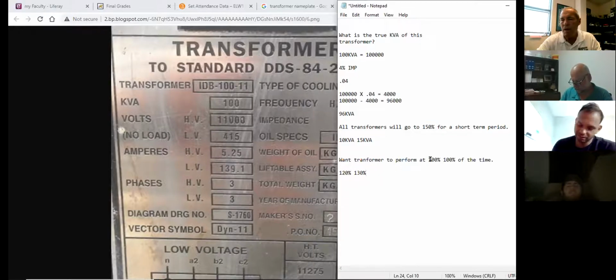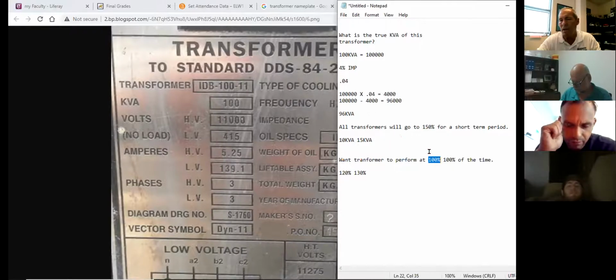All right, goes back to a nice calm day, it's 100%. I think you guys got to realize here, my 100 kVA transformer is going to cost me about $10,000 a piece. Damn, so they're not cheap. So I want to get the most I can out of this transformer all the time, and that includes seasons. If it's spring and fall and it's nice calm days outside and I'm not using as much electricity, I want it to be around 100%. When it gets real cold or real hot, it can go over a little bit, but I don't want it to break 150%. It's a fine line we're trying to drive there. Does that make sense?